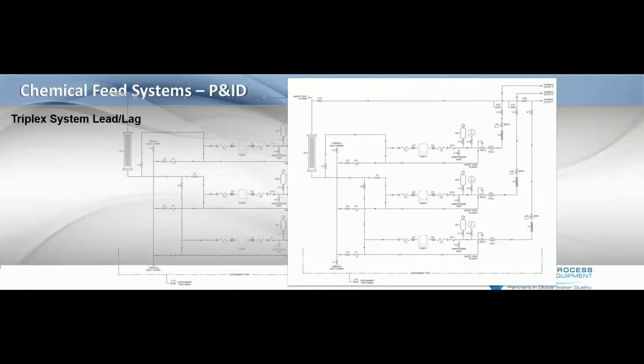Basically, it's from one base. You may sometimes see, not chemicals reacting, but 3 pumps where 2 are on a critical chemical, and then 1 pump on the triplex, which would have a separate feed and calibration column, could be utilized for another chemical at that point. So that is common and does come up from time to time. Generally speaking, it's 1 chemical per base, but sometimes they build longer systems designed to operate like that.